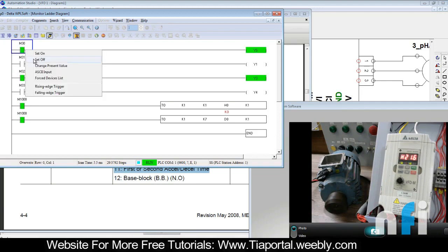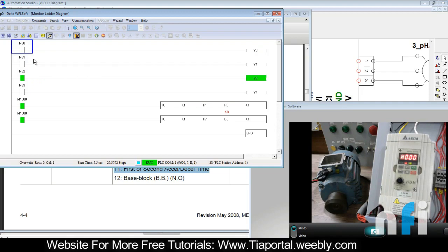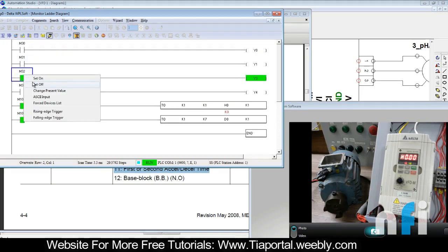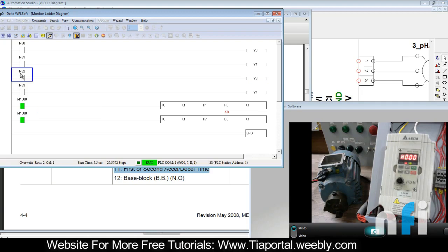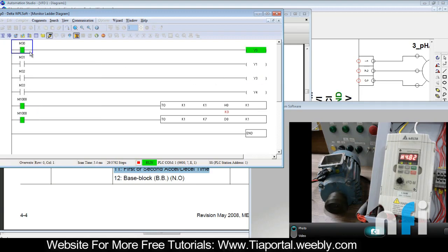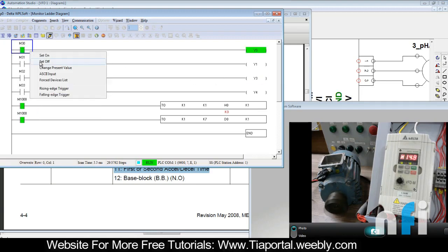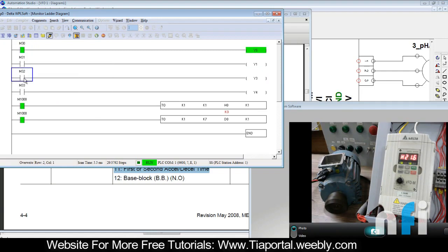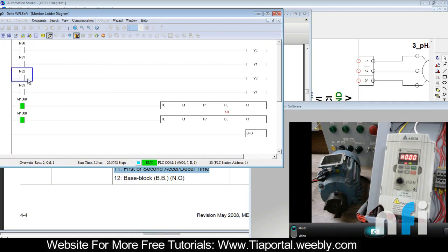If I stop, it will stop immediately - that's the second acceleration. If I want to go back to the first one, I'll set M32 off. Now when you run M30, it will again go smoothly and stop smoothly. That's the selection between acceleration and deceleration times in your drive. You can quickly change the situation even when the motor is running.